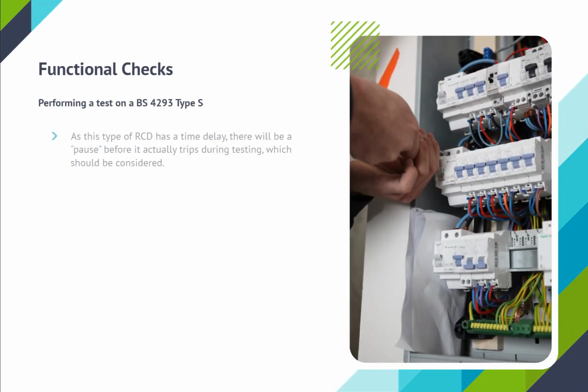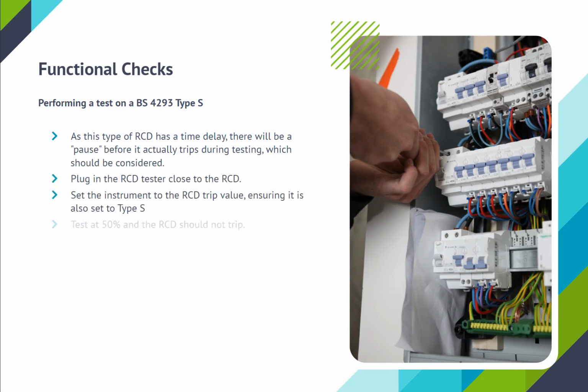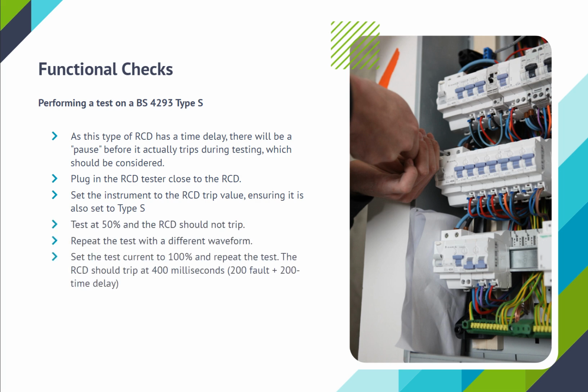Performing a test on a BS4293 Type S. As this type of RCD has a time delay, there will be a pause before it actually trips during testing, which should be considered. Plug in the RCD tester close to the RCD. Set the instrument to the RCD trip value, ensuring it is also set to Type S. Test at 50%, and the RCD should not trip.